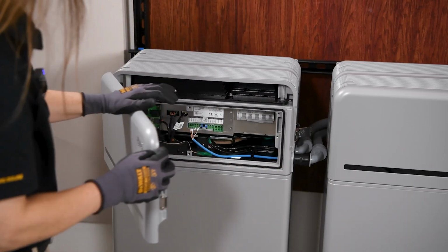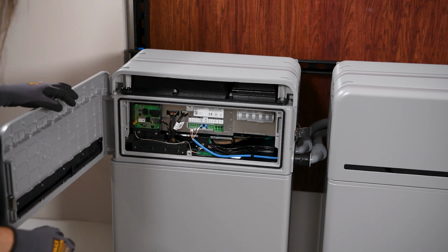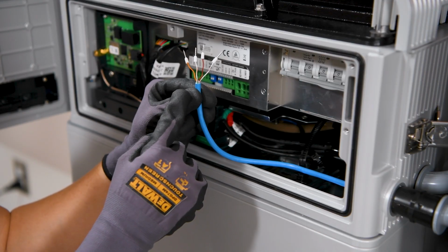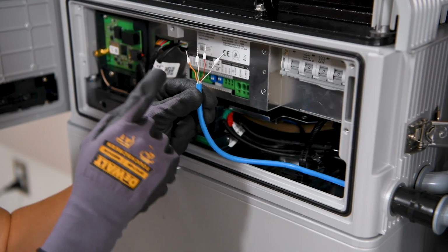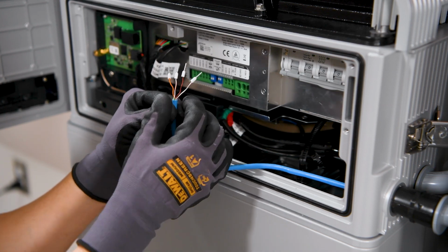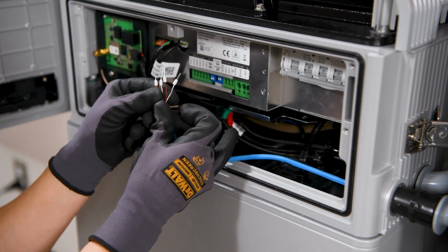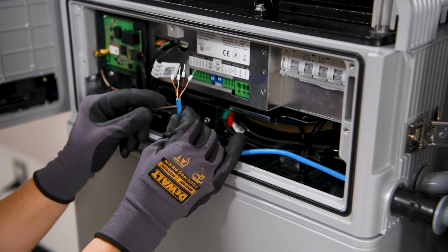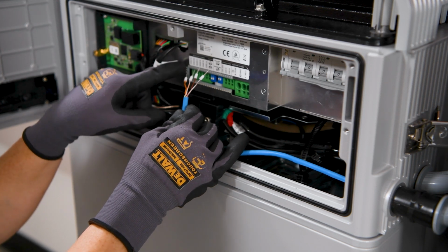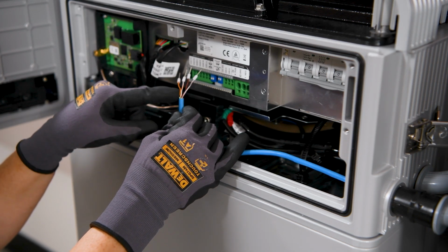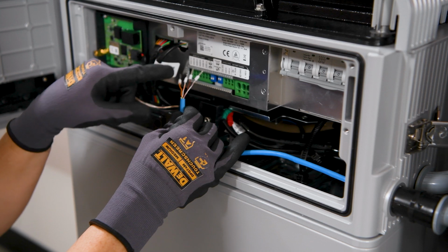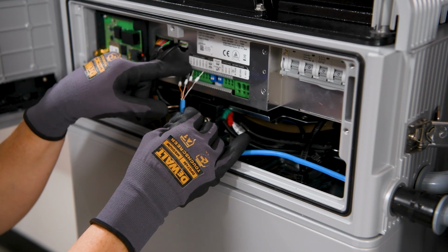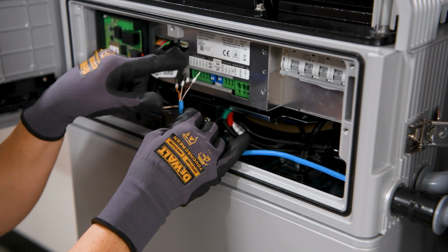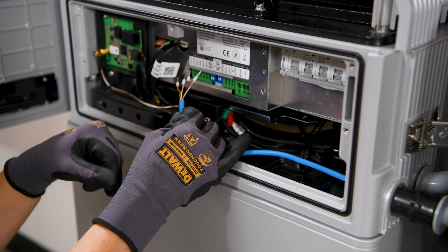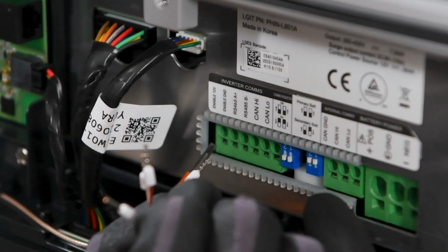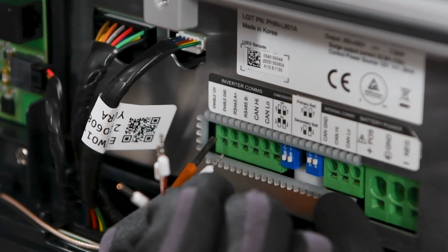Let's get started with communications on our primary battery, using the same colors we connected inside the inverter. We've ferruled the ends and will connect them just as we did inside the inverter: orange for enable 12 volt, white orange for enable ground, brown for RS485A+, and white brown for RS485B-. You'll insert your ferrule end inside the round portion of your terminal.